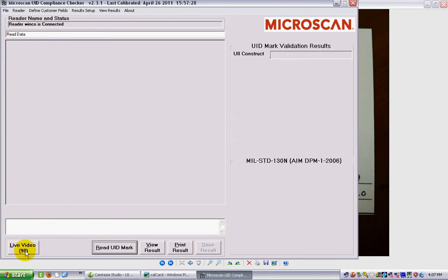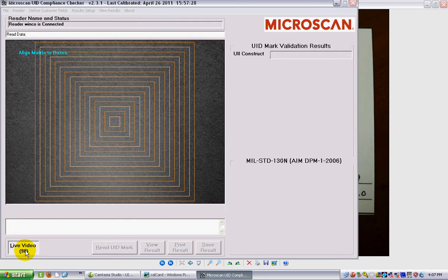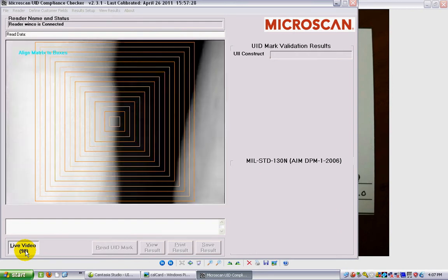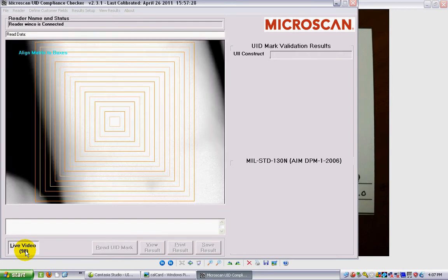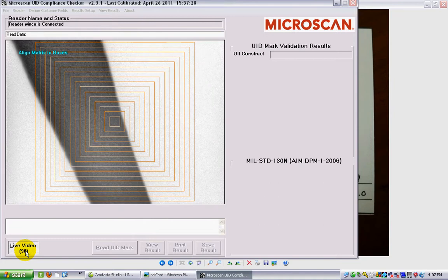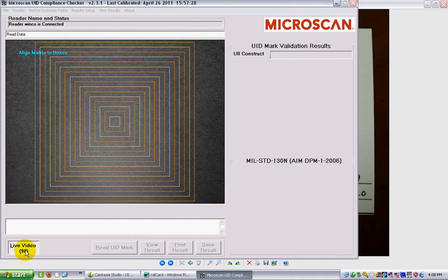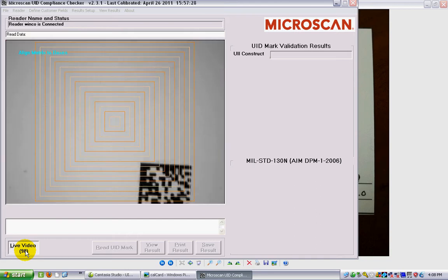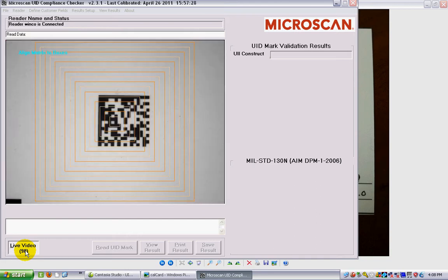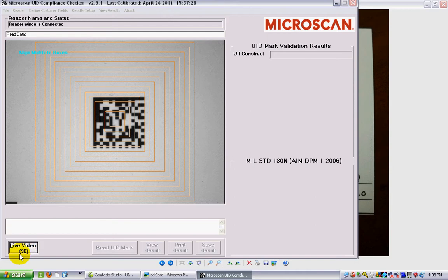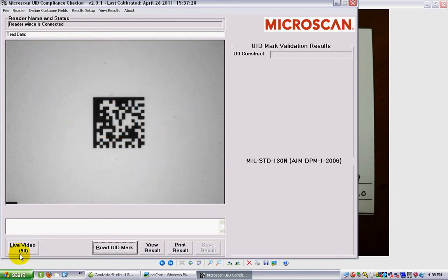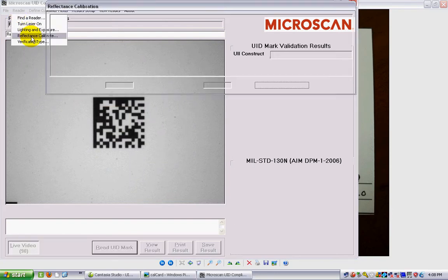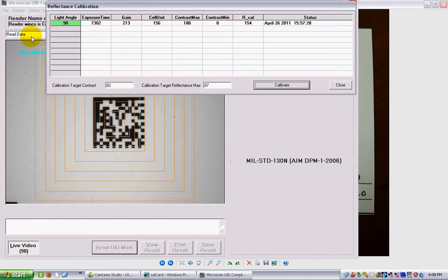Just to show that it's working, if I click on live video here and I wave my fingers underneath it, you can see that it is actually a live video there. What I'm going to do is put my calibration card underneath the reader. I'm going to turn off the live video at this point and go into the reader menu and choose reflectance calibrate.